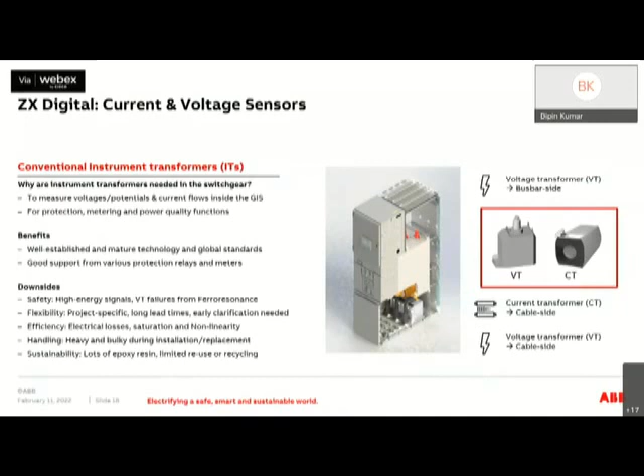So one thing what we have done is replacing the conventional current and voltage transformers with current and voltage sensors. The conventional current and voltage transformers, yes, we have been using them for decades now, and they are doing their work. But there are some potential disadvantages, as CT sometimes fails because of saturation, VT sometimes fails because of ferroresonance, and then these are fixed to certain ratios.